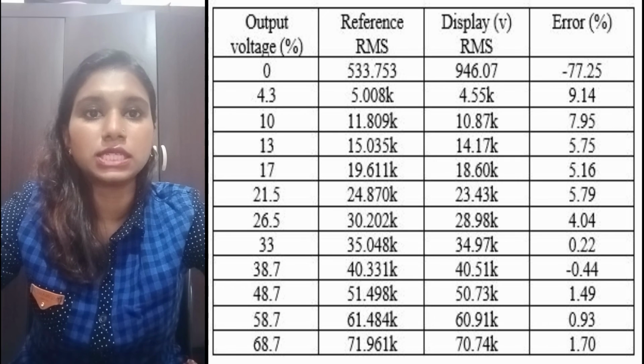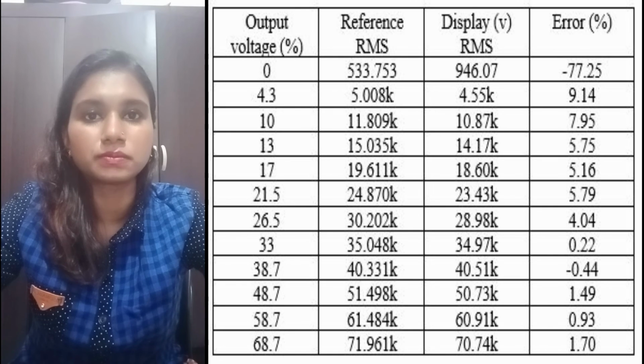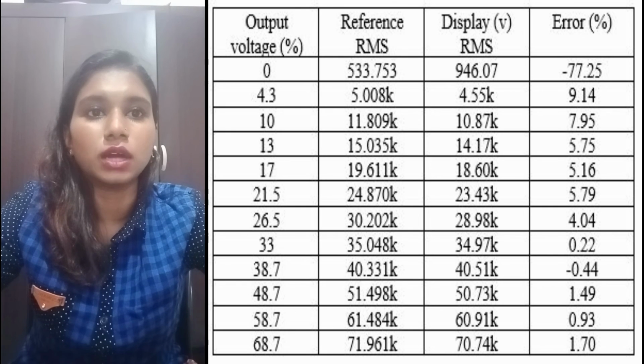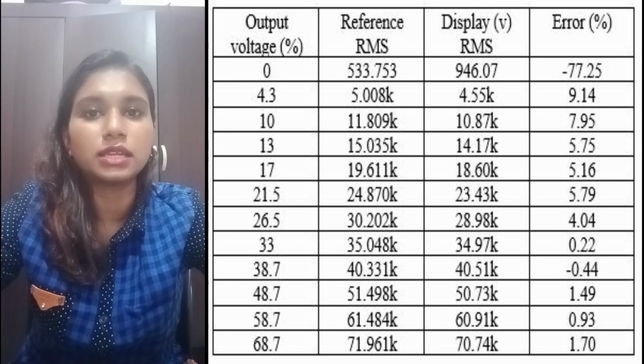The output voltage is adjusted, and when the output voltage increases from 0 to 68.7%, the reference value of RMS also increases, except for the output voltage of 0%. The display value of RMS also increased. The percentage error for the output voltage is not steady. Sometimes the error is lesser, then it goes up, and sometimes it is a negative value. The percentage of error may come from machinery error or calibration error. These types of technical errors can cause the reading to not give an accurate value. To obtain an accurate value, the user must take readings many times and take the average.